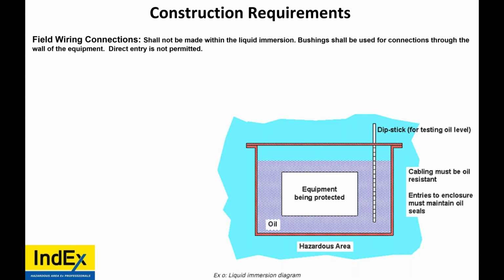When you look at an oil-filled transformer, see this sidewall. If there was a hole here, the oil is going to spill out. If you had a plug there and you wanted to put in a cable, the oil will come out. If you put a cable gland there and a cable, the oil will go up the cable or down the cable. Field wiring connections shall not be made within the liquid immersion. Bushing shall be used for connections through the wall of the equipment. Direct entry is not permitted.